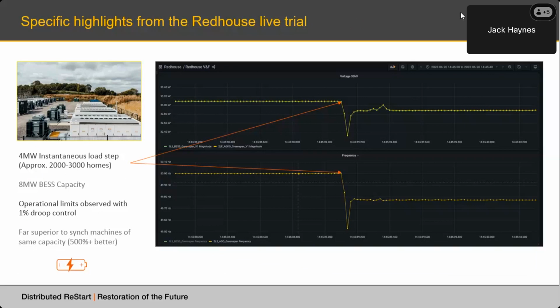You can see in this example, where the orange arrows are pointing, that's the point where the instantaneous load of 4 megawatts was implemented. Within about 2 or 3 cycles, so around 60 milliseconds, the BESS has already recognized the additional load present in the island, modulated its output to cope with that, and then settled at the expected voltage and frequency as per its voltage and frequency droop control settings. And you can see it only deviating to around 49.5 hertz in this instance.